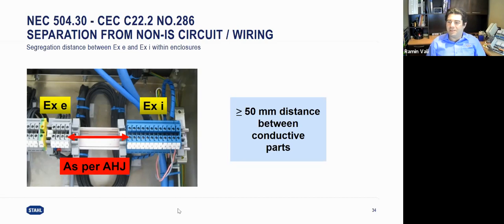So that's 5 centimeters or 2 inches. Usually it is based on the authority having jurisdiction, but it's always recommended. Inside the panel, the non-IS and IS signals have to be 5 centimeters apart. And when it comes to the wiring, they also have to be 5 centimeters apart from each other.